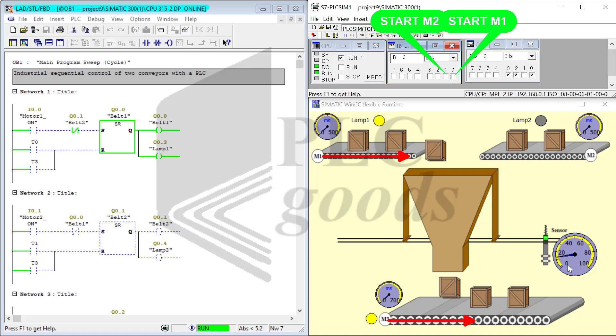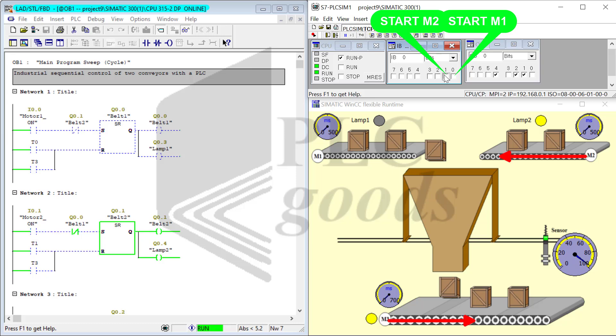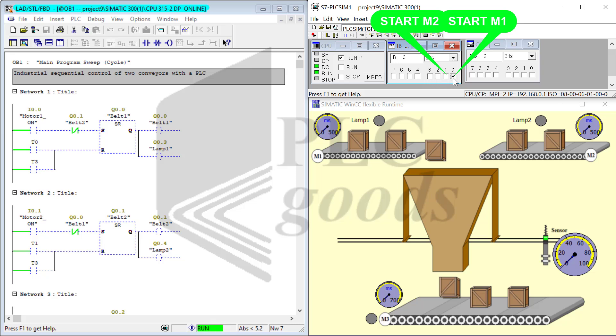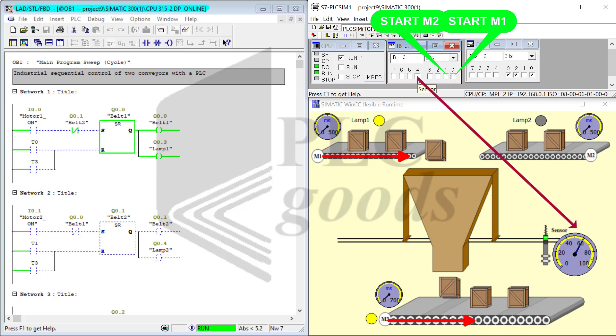M3 is deactivated after the 10-second period ends and then after a further 7 seconds. I go ahead and start M2, and notice that the same behavior is repeated. To maintain the system's operation, the sensor needs to detect movement of at least one box within every 10-second interval. If no movement is detected within this time frame, M1 or M2, and finally M3, are deactivated.